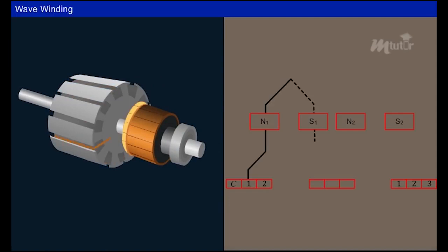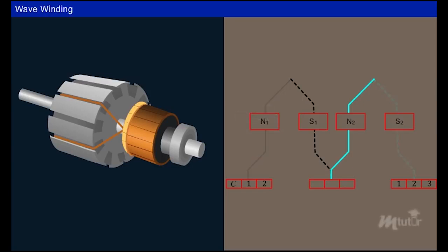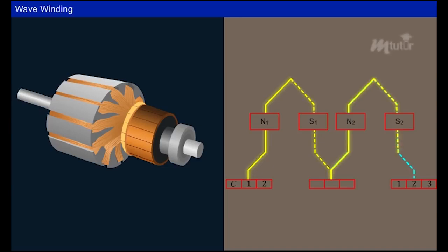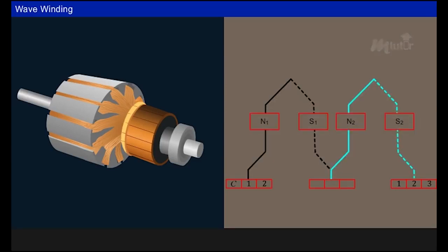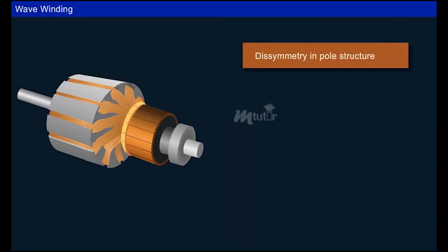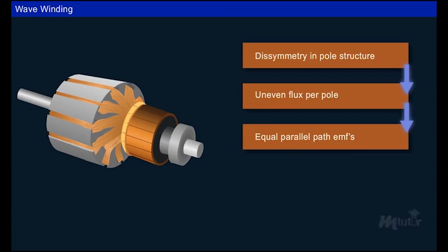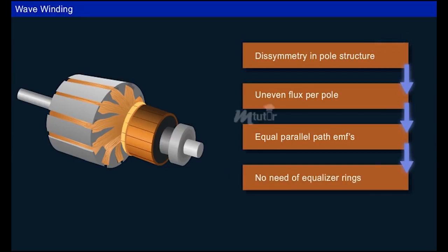Now we shall learn about wave windings. In this type of winding, the completing end of a coil is connected to the starting end of another coil under a different pole pair, moving ahead and avoiding overlapping. The appearance of this coil winding resembles a wave, hence the name wave winding. Regardless of the number of poles, the number of parallel paths is always equal to two. Therefore, even with unequal flux distribution due to asymmetric poles, the EMF in both parallel paths is the same, so no equalizer rings are required.